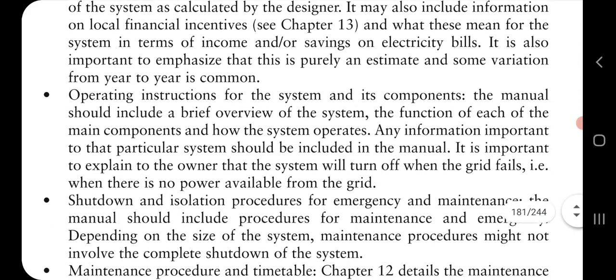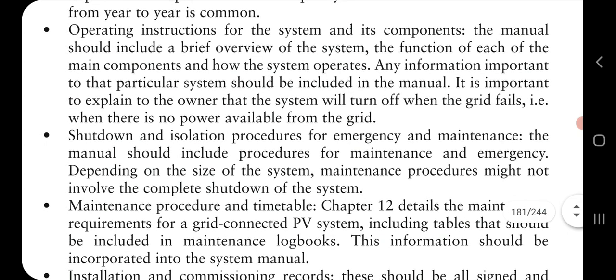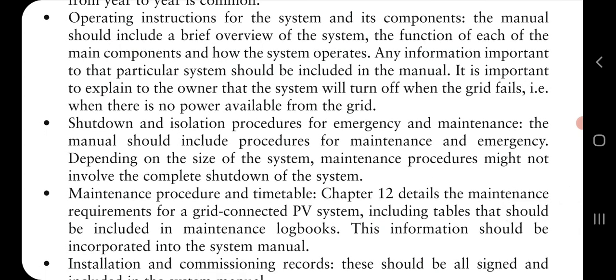Then operating instructions in the system manuals have to be provided to the owners, indicating how it works, how it operates, and information regarding the equipment. It has to be explained that the system stops and turns off when the grid fails, along with shutdown and isolation procedures for emergencies and maintenance. A manual should be provided for if an emergency happens or any maintenance is needed, how the maintenance has to be done and how the complete shutdown has to be done. All the procedures have to be given there.